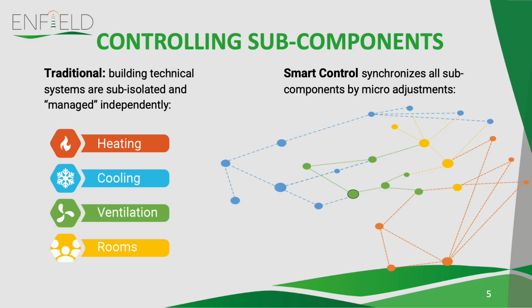Instead of doing that, we could heat maybe a little bit in the morning because we know that after that, in any case, it will be quite hot, and we can postpone the start moment of the cooling system, and it already saves a lot of energy. But it requires using more information, and it requires controlling all the devices together within one single control framework.